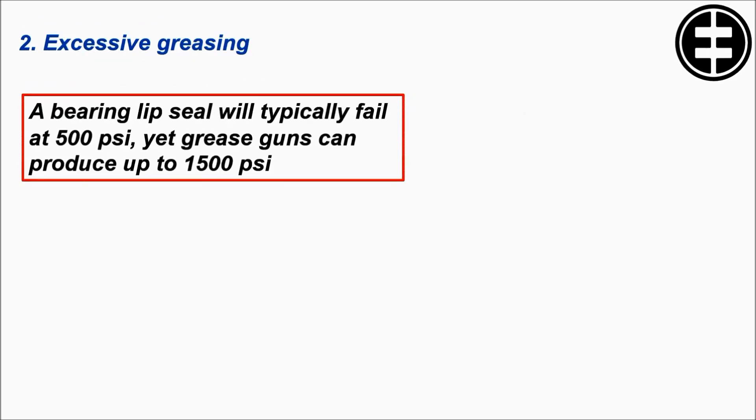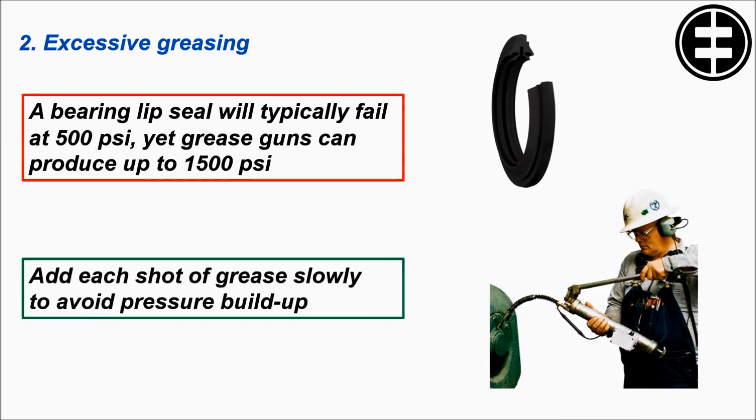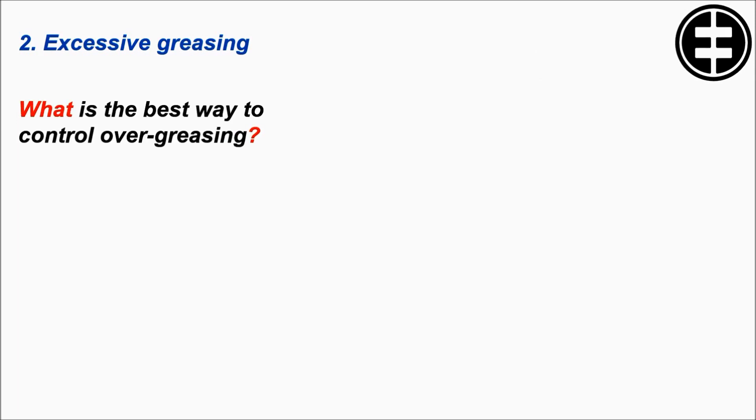A bearing lip seal will typically fail at 500 psi, yet grease guns can produce up to 1500 psi. Add each shot of grease slowly to avoid pressure build-up.